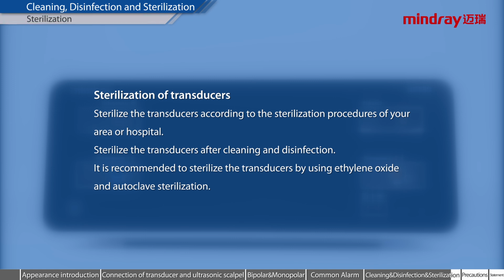Sterilization. Sterilization of transducers. Sterilize the transducers according to the sterilization procedures of your area or hospital. Sterilize the transducers after cleaning and disinfection. It is recommended to sterilize the transducers by using ethylene oxide and autoclave sterilization.